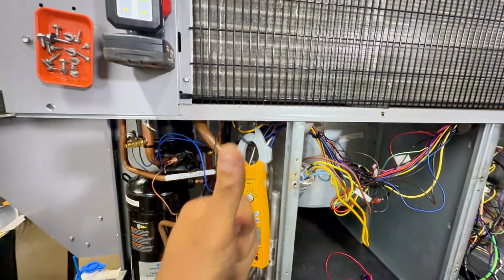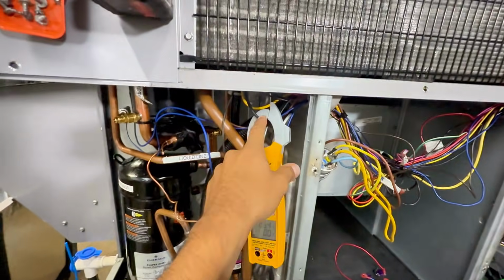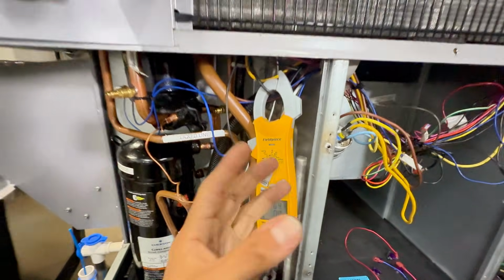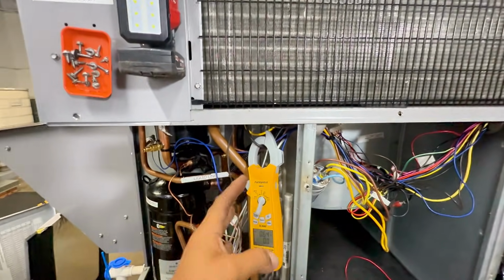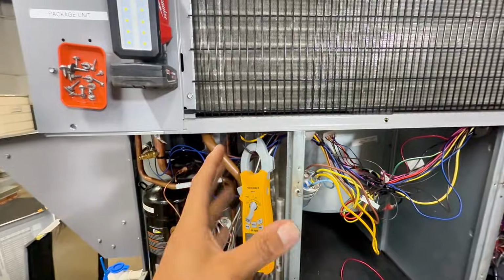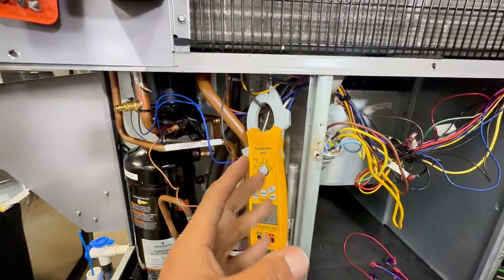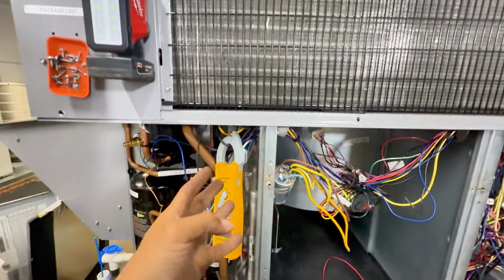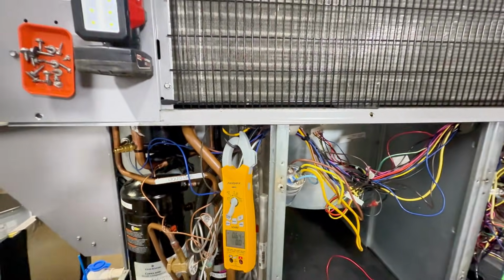Of course, find out what the full load amps is, put it on the right wire. By checking that amp draw though, it can tell you what is going on with the condenser fan motor. We always want to be around that full load amp. And that's just another way to troubleshoot and diagnose how well that motor is working.